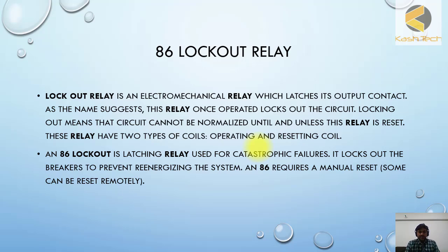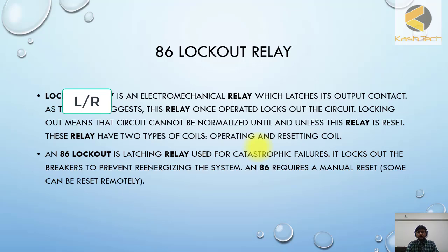These relays have two types of coils: operating coils and resetting coils. A lockout relay is a latching relay used for catastrophic failures. It locks out the breaker to prevent energizing the system, and code 86 requires a manual reset or it can also be electrically reset from remote. The lockout relay can be used to trip the breaker while simultaneously locking out the closing pulse.